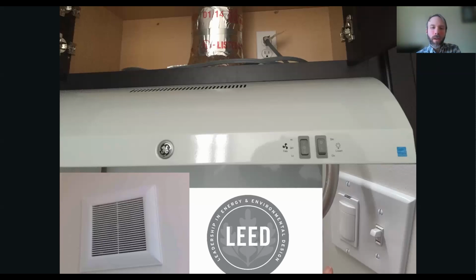Now, the systems must also give the occupant control to turn them on, off, or adjust the speed. Note, this is one area where we see major problems and failures, both in deficiencies in the range hoods and bath fans on many of our LIHTC projects. Using the LEED integrative project process and preliminary rating process, whether you're using LEED or not, you can design out these failures and reduce the risk by building in higher ventilation rates during the preliminary rating, ensuring that the mechanical contractors are testing these systems, and ensuring that proper wiring controls of systems are implemented by the electrician on the first couple of units. This is important for a trained project team.